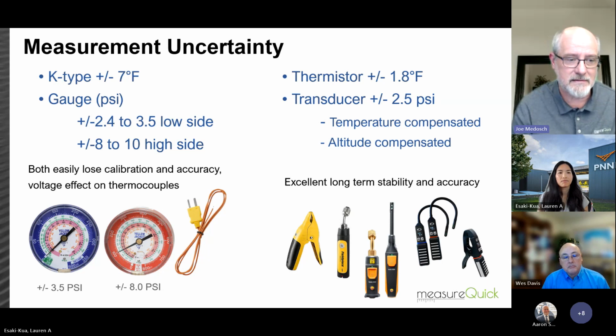If you start adding these uncertainties up, it's really difficult to know that your charge is correct. You have to be dead on exactly what the number should be to conclude that you have the correct charge. Meanwhile, these great new smart probes give us nothing that's dead on accurate, but they have an accuracy that gives high confidence. They're measuring to a fraction of a decimal, sometimes two, rounded up, so we know we're getting accurate measurements with these devices.